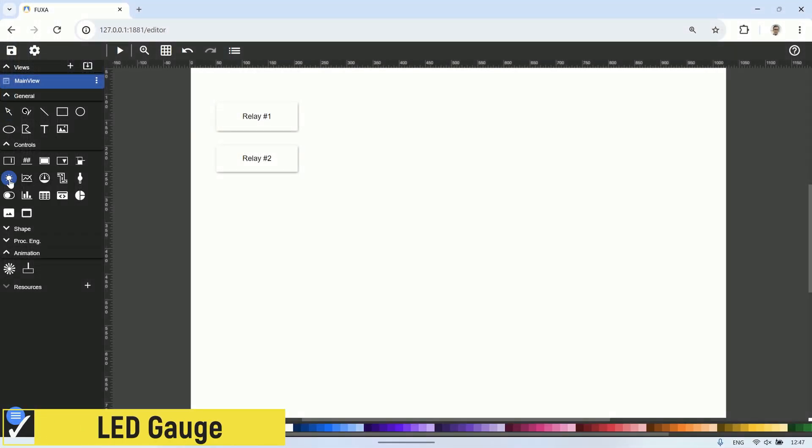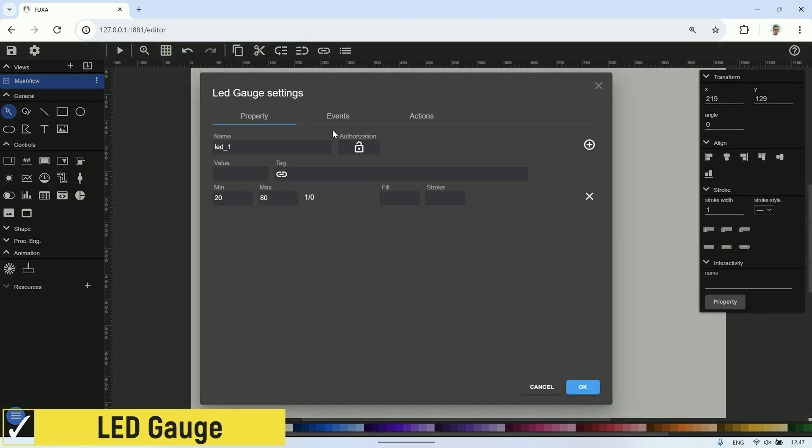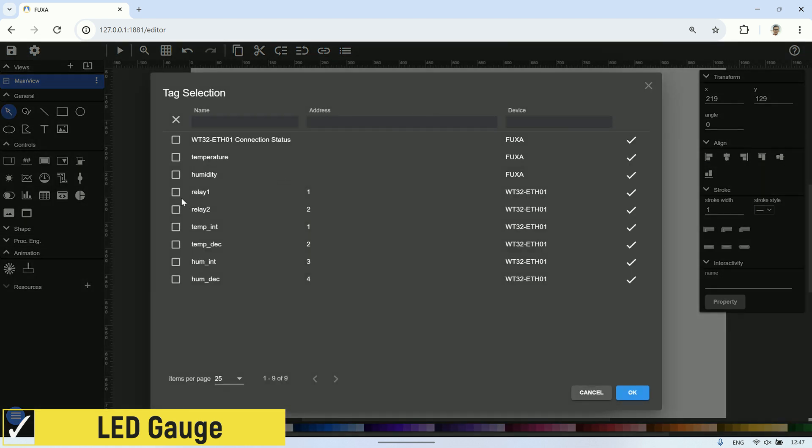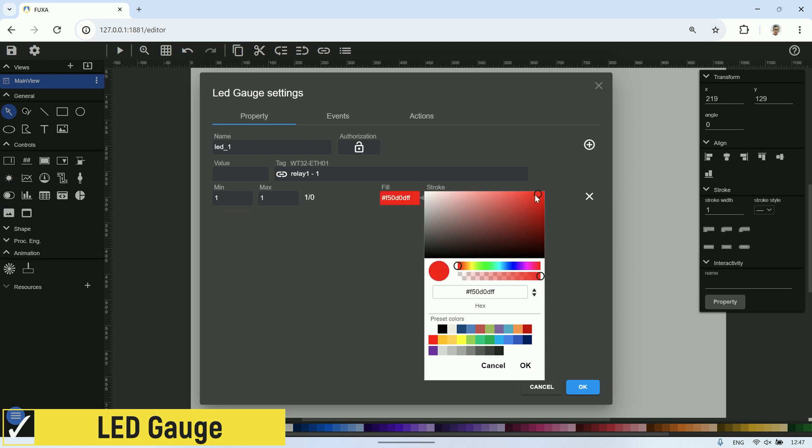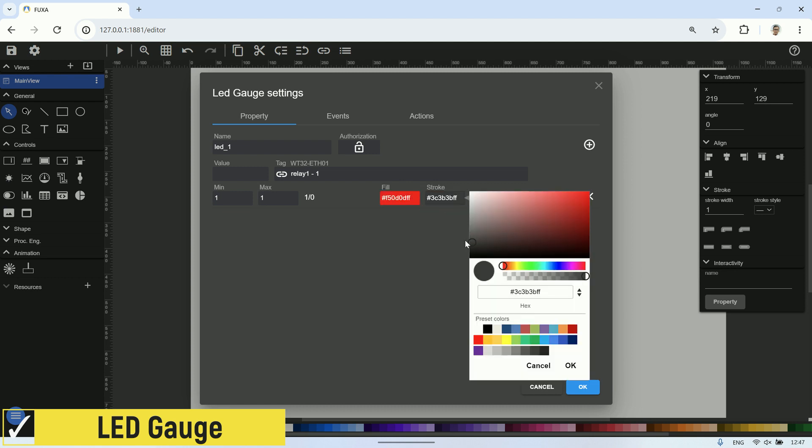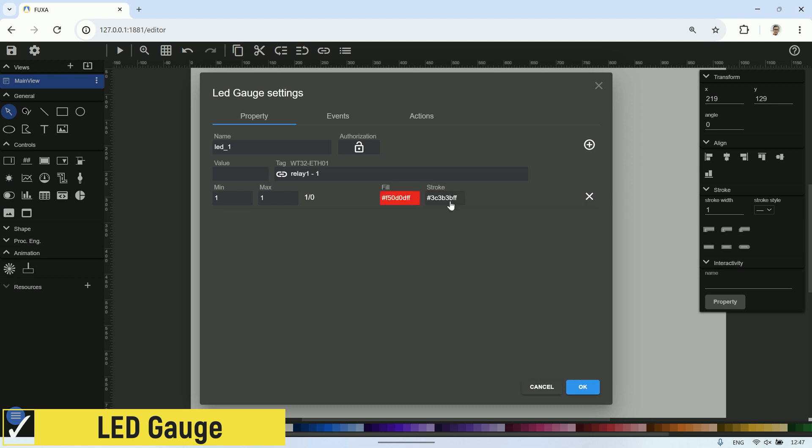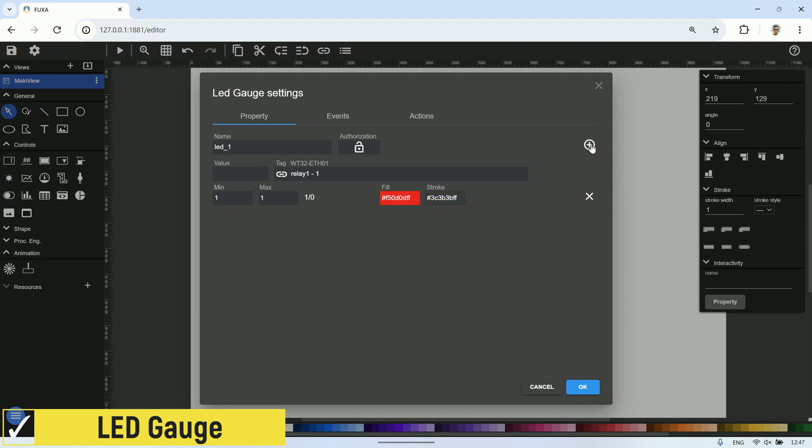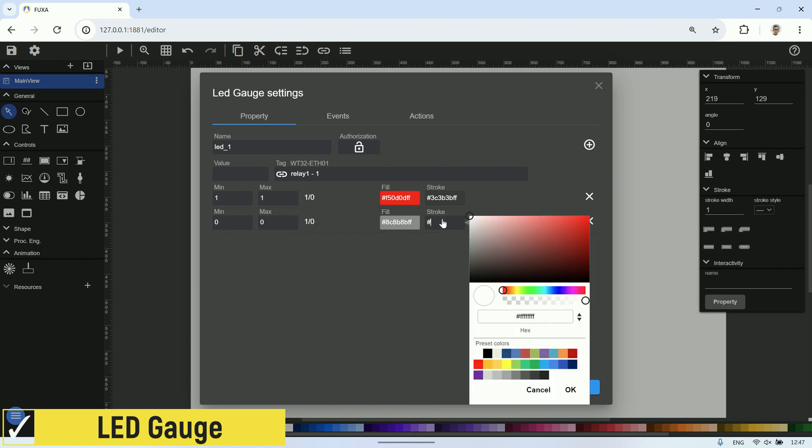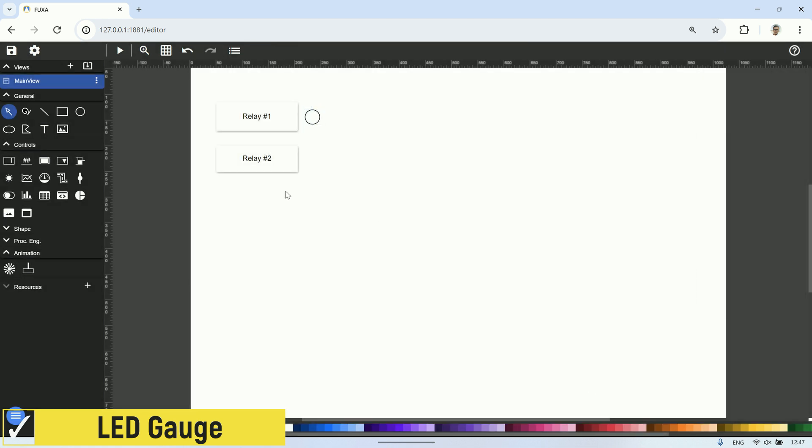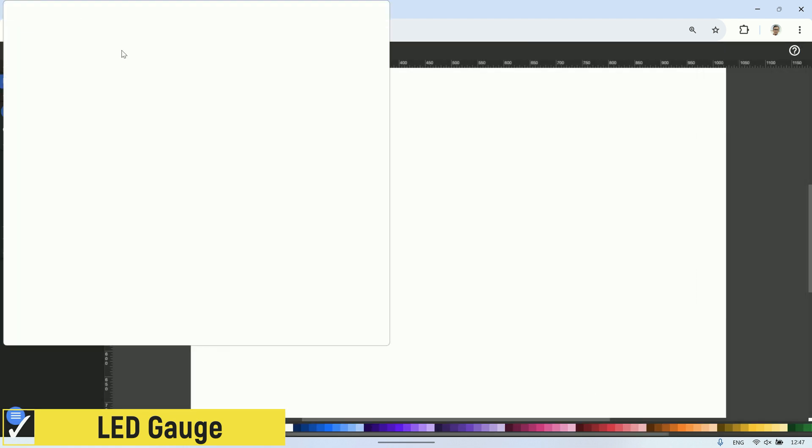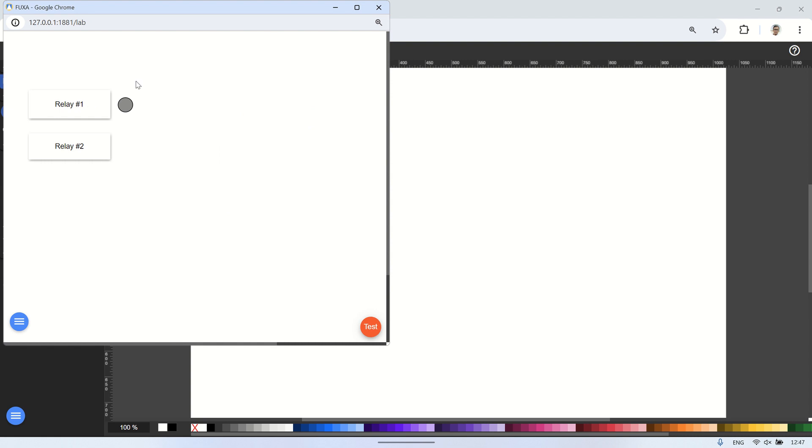Next, let's try using LED gauge visuals to display the status of relay number one and relay number two. Select the relay one tag in the LED gauge settings. Then, in the property tab, set the min to one and max to one. This means if the tag value is one or true, choose the desired fill and stroke colors. Add a condition for when the tag status is false or zero. Set min and max to zero, then choose the fill and stroke colors for this state. Click OK and let's test it out. We can see that when the relay one button is pressed to turn on relay one, the LED gauge changes its color according to the relay status.